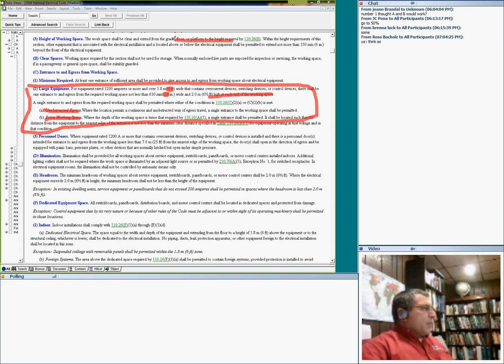Here's my switchgear. The switchgear is located here, and the door is right in front of it. That's called unobstructed. You don't need a second door if the distance is short. Here's the switchgear, guys. It used to be four feet, and I make this 8 feet. I hold the clearance, the room. Okay, that's a big deal.